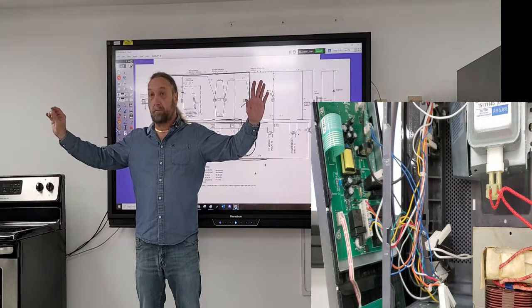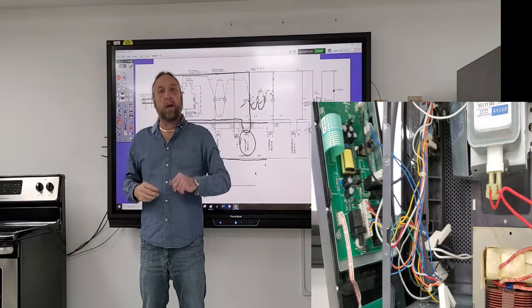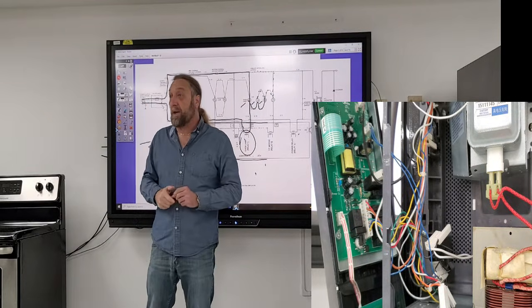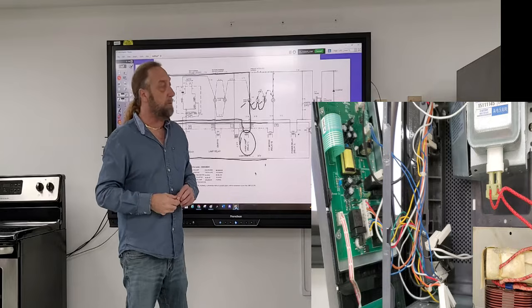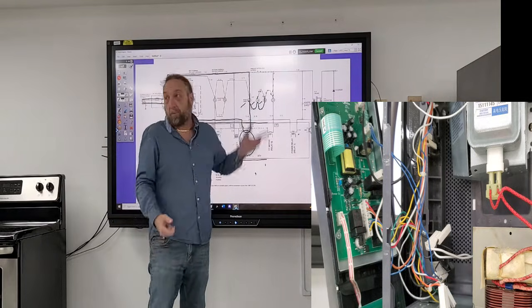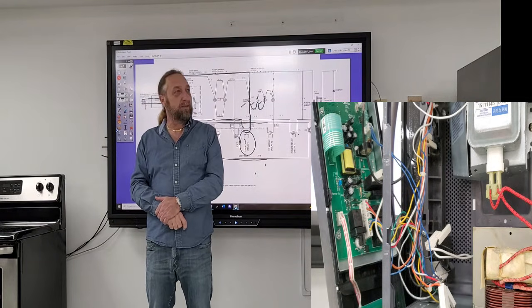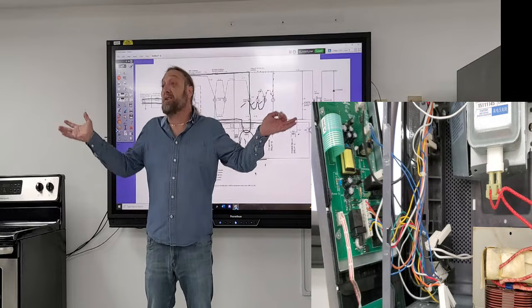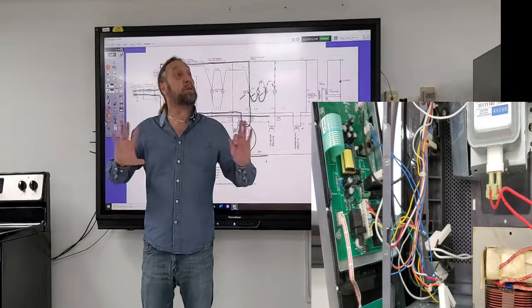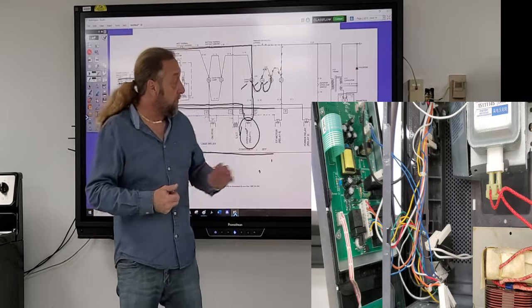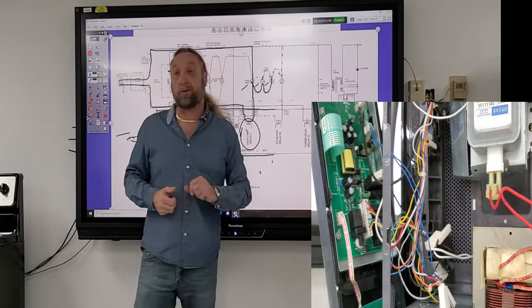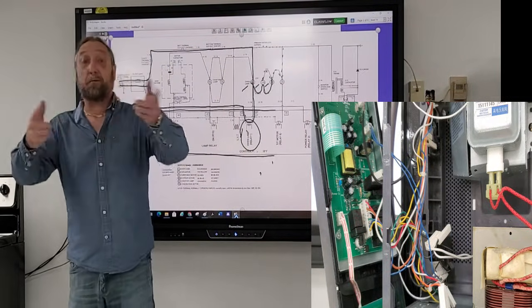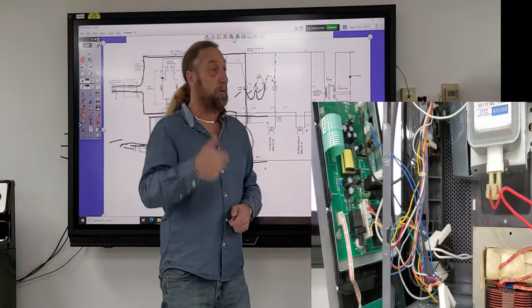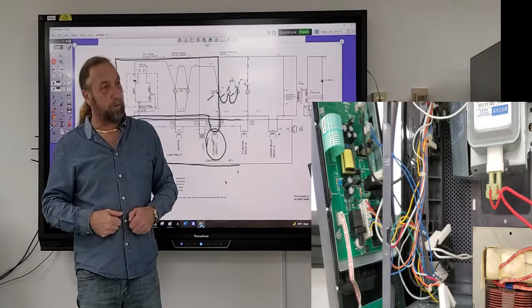Period, it's a transformer problem. Wait, are the fans and turntable working? Yes, they're working. Then what? My primary door switch is good, and the monitor has nothing to do with cooking, so the problem is not the door switches. So the problem's the relay or power to the transformer. My first statement to you is, Imran, I need to check power to the transformer.